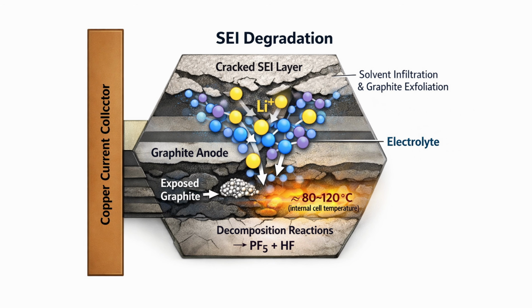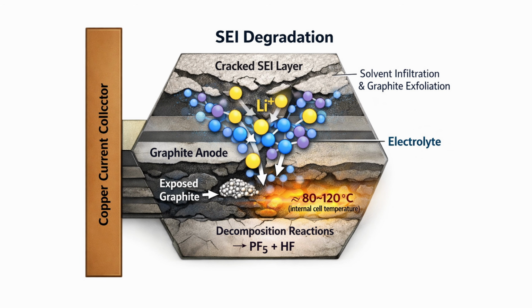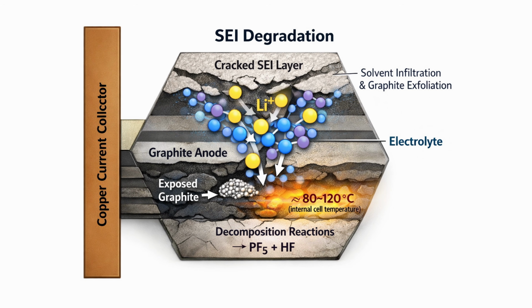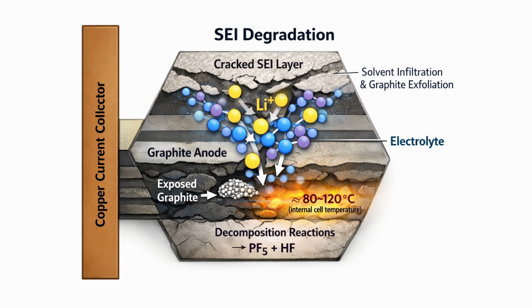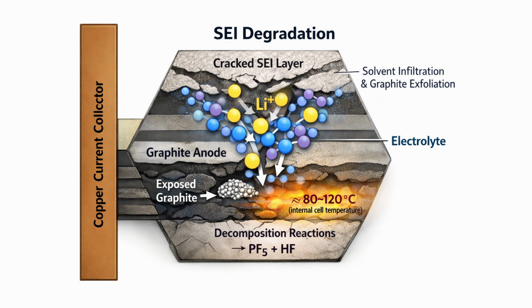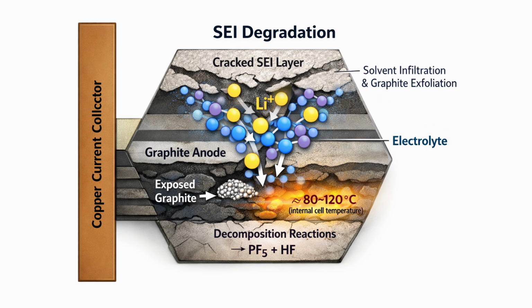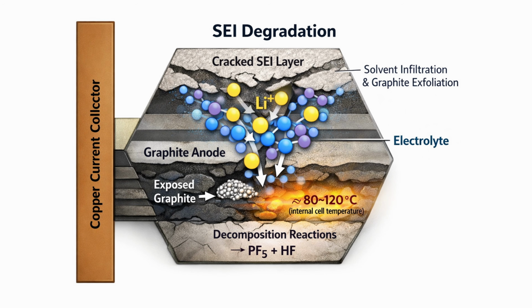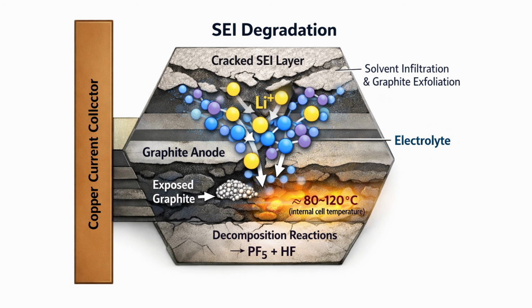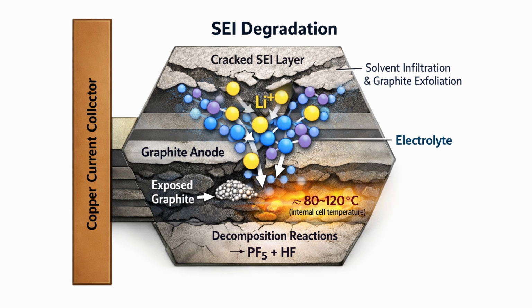So it's important to quickly go through the stages of thermal runaway inside a battery like ours. When a thermal runaway is triggered, the first thing that happens inside a cell is the protective layer on the graphite anode starts to break down. Inside that cell, the temperature rises to around 80 to 120 degrees Celsius. This is not a very fast process. It can take up to tens of minutes.